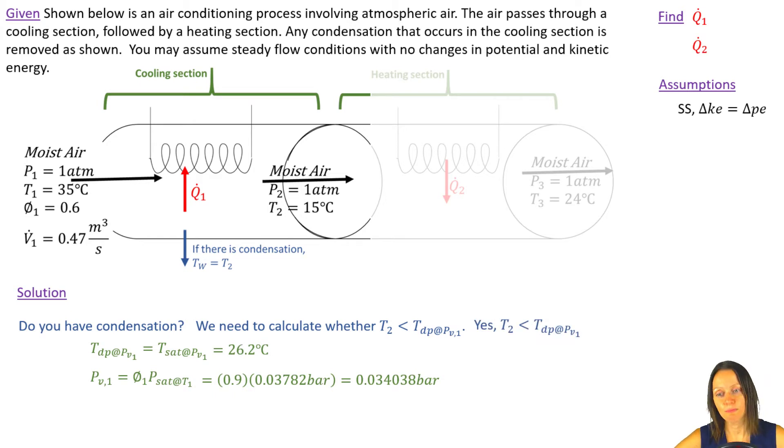So that answers the question. T2 is 15 degrees Celsius, and that's less than 26.2, so I've cooled below the dew point temperature. I do have condensation.